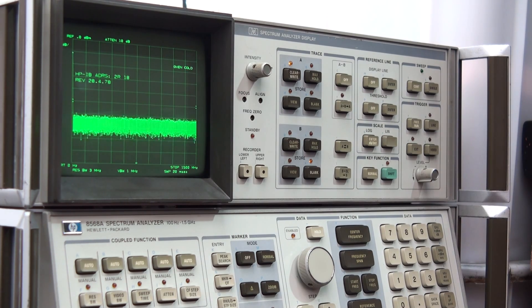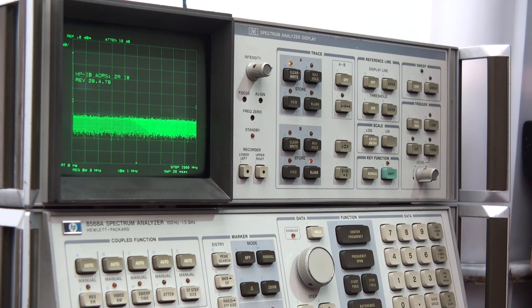The other problem it did have, and it hasn't done it today, so I might have repaired that. It's got an internal backup battery, which is basically three NiCAD batteries. And all that does is store data and calibration data and setups in the calibration routines and things like that.